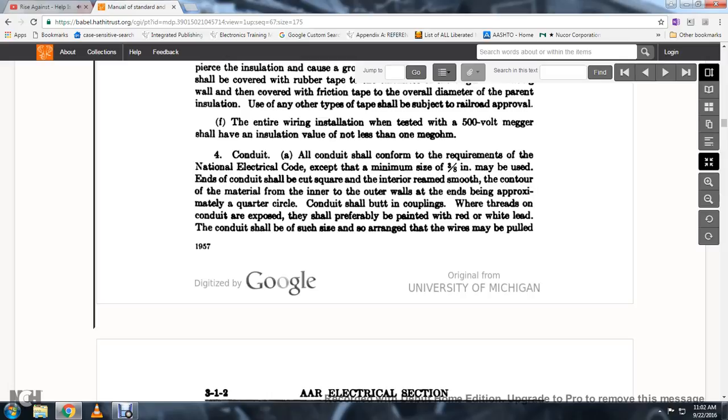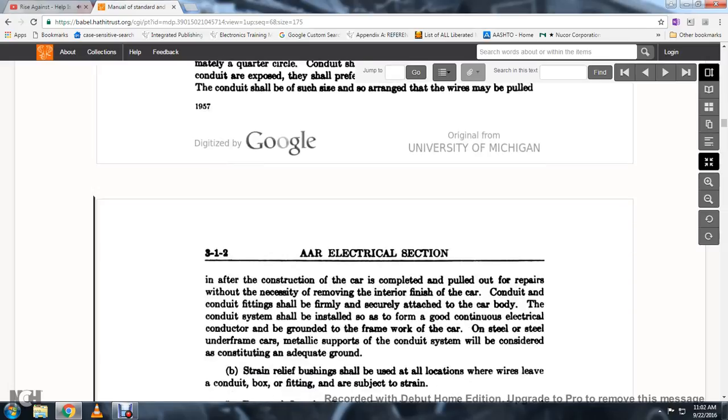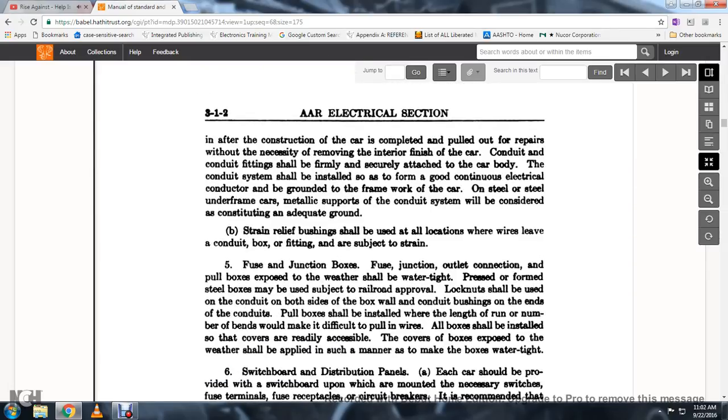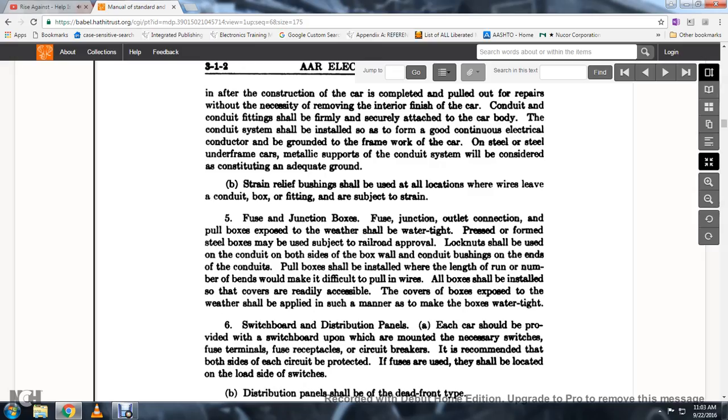The conduit shall be such size and arranged that wires may be pulled in after construction of the car is completed and pulled out for repairs when necessary without removing the interior finish of the car. The conduit and conduit fittings shall be firmly and securely attached to the car body. The conduit system shall be installed to form a good continuous electrical conductor grounded to the framework of the car. Steel underframes and metallic supports from the conduit system will be considered as constituting adequate ground.